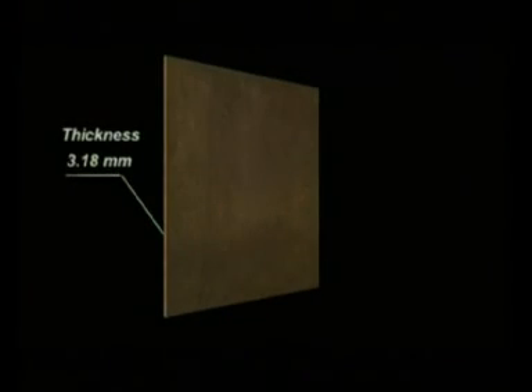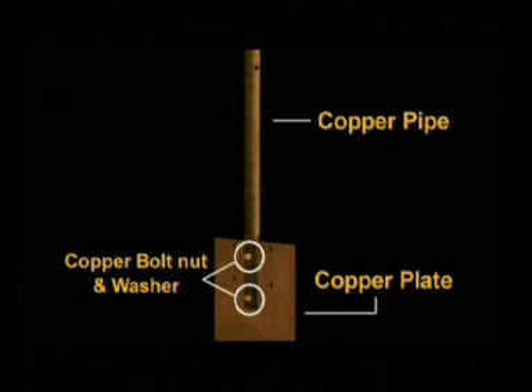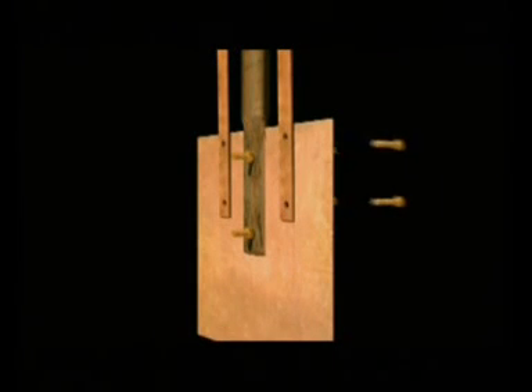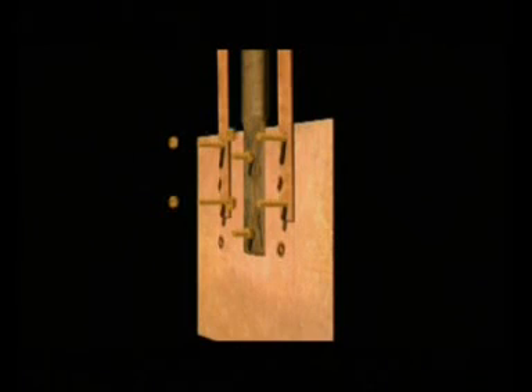The thickness of this copper plate should not be more than 3.18 mm. Right in the center of the plate, a copper pipe is fixed with the help of a braze or bolts. Remember that since the plate is of copper, the pipe, bolt nut and washer all must be of copper. 2 copper strips which are 6 mm thick and about 3 to 4 cm wide are then brazed or bolted onto the copper plate. 1 more copper strip is bolted or brazed onto the copper pipe and the 2 strips.